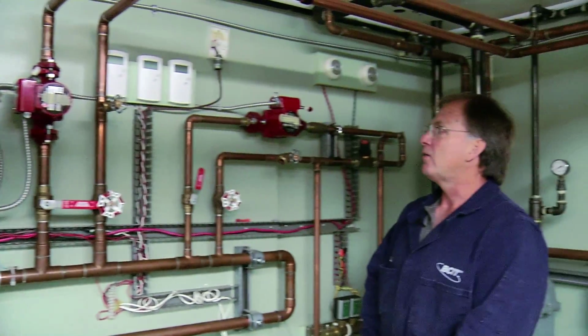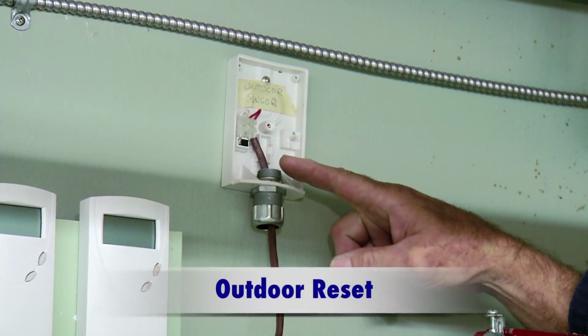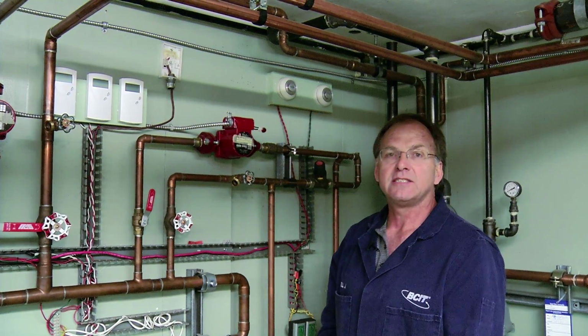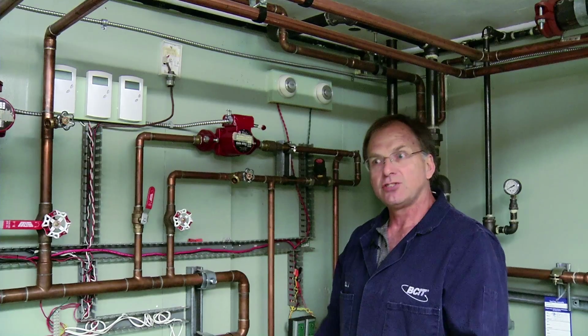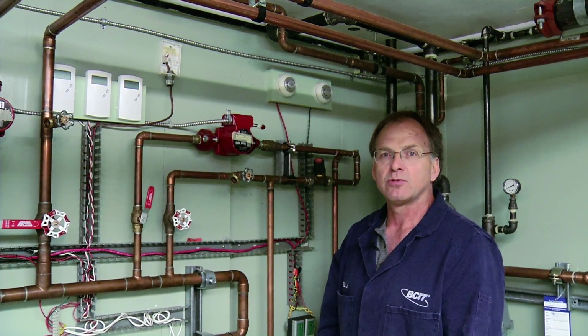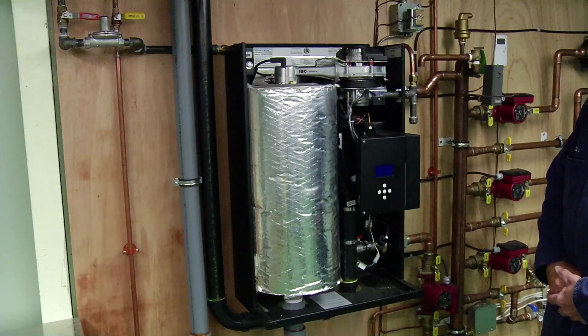Another example of how technology can reduce the energy consumption in a hot water heating system is to use an outdoor reset. This is a device that would actually go outside, and it's a temperature sensor. That temperature sensor could come back down to the mechanical room into your control panel and actually change the temperature of your water. Now what it's doing is indicating what the heat load is. The heat load comes from the outdoor air temperature, and it will adjust the temperature of your boiler water to exactly what is required to heat the system and keep you comfortable.